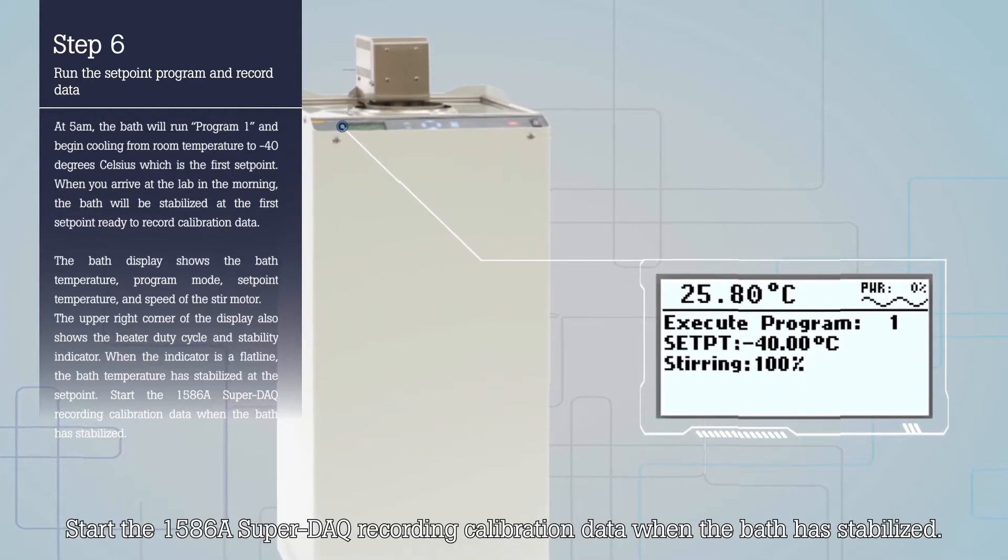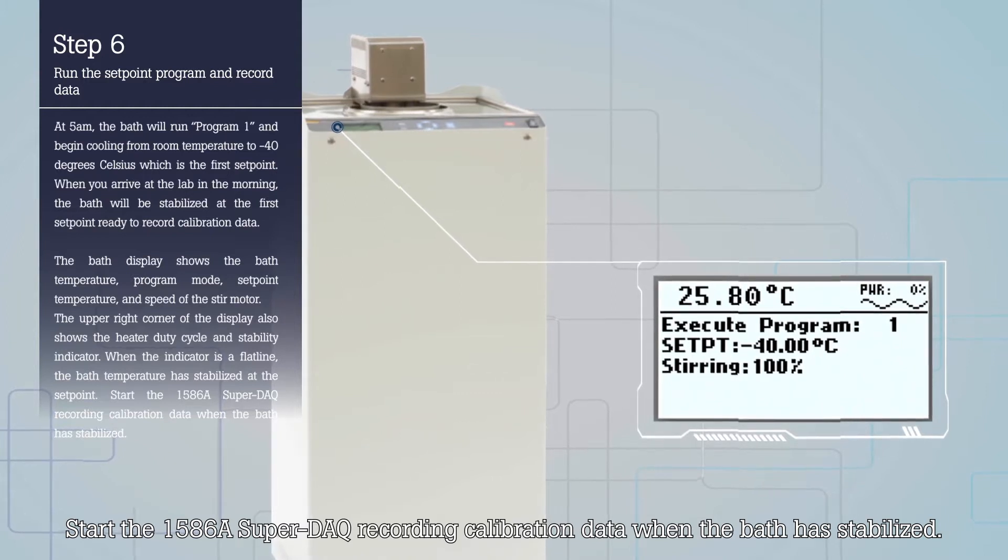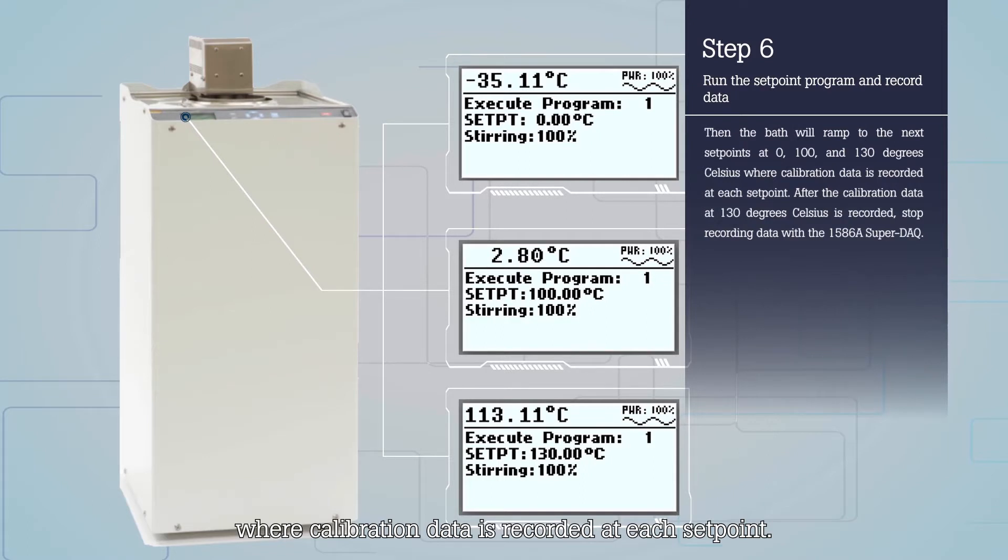Start the 1586A Super-DAQ recording calibration data when the bath has stabilized. Then the bath will ramp to the next set points at 0, 100, and 130 degrees Celsius where calibration data is recorded at each set point. After the calibration data at 130 degrees Celsius is recorded, stop recording data with the 1586A Super-DAQ.